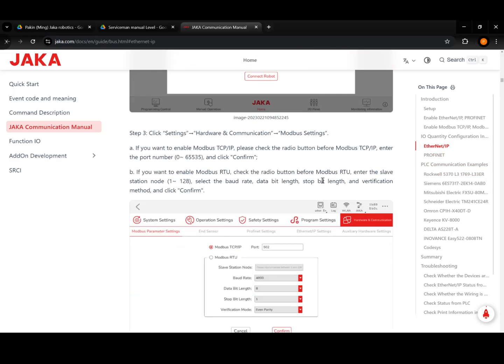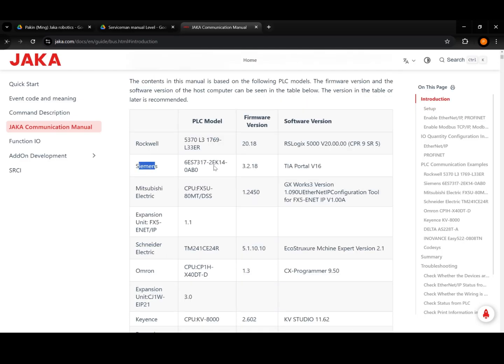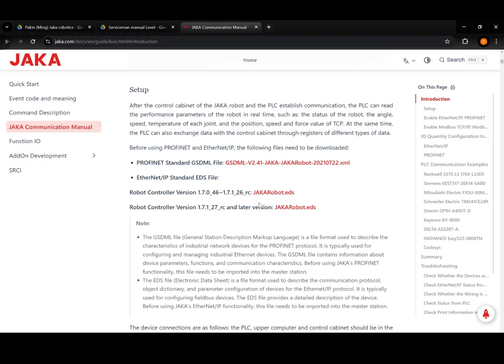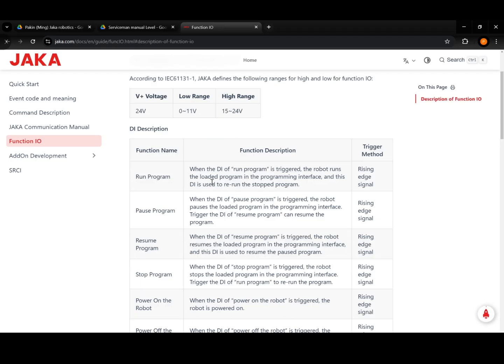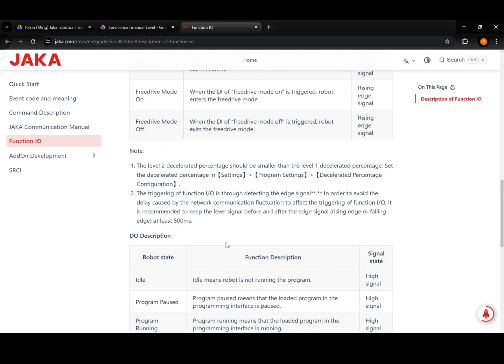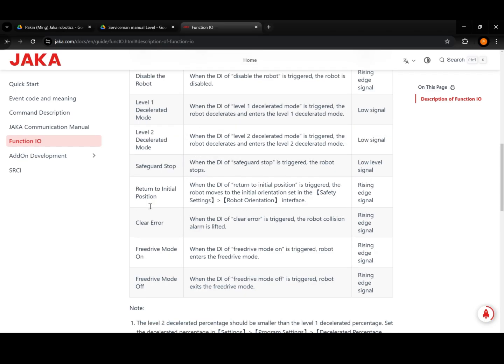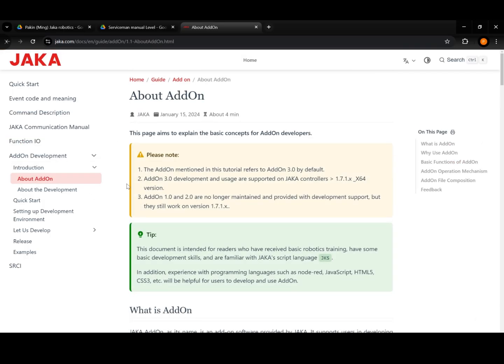And for the Ethernet IP file, when you're using this manual and you want to find the EDS file, we have already provided it in here, and for Profinet, we also provide the XML file already in here. When you're using the EDS file, you need to be concerned about the version of the controller. If you're using the latest version, you need to use this file, and if you're using the old version, then you need to use this file. And the function I/O. This function I/O will tell you the purpose of each function. It's very useful for you when doing the integration by using this I/O. And here's a method of how to add on, but I will talk about this later.